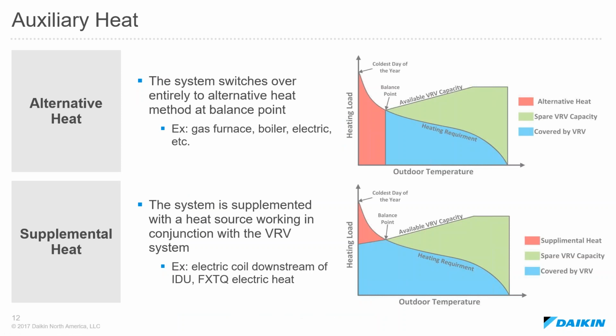Now there's really a few different types of auxiliary heat that can be used for this balance point concept. The first one being alternative heat, and what that essentially means is you're switching over from air source heat pump heating to an auxiliary source, for example, a gas furnace. So you're switching entirely over. You're not operating those both at the same time.